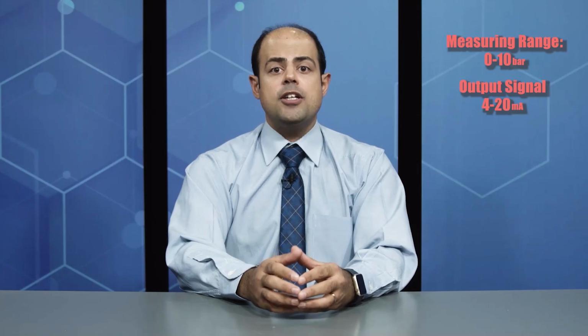You can imagine a control valve which is controlled by a pressure transmitter signal. The measuring range is 0 to 10 bar and output signal is just 4 to 20 milliampere. Unfortunately, this transmitter has not been calibrated for a long time. Therefore, the accuracy has decreased from 0.5% to 2%. The valve used to open 50% as a result of the 12 milliampere signal, but now it does not happen. Why? Because the pressure transmitter cannot measure 5 bar accurately.